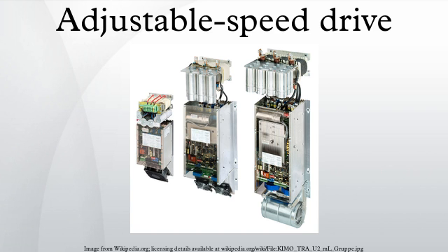Hydraulic adjustable speed drives. There are three types of hydraulic drives: hydrostatic drives, hydrodynamic drives and hydroviscous drives. A hydrostatic drive consists of a hydraulic pump and a hydraulic motor. Since positive displacement pumps and motors are used, one revolution of the pump or motor corresponds to a set volume of fluid flow that is determined by the displacement regardless of speed or torque. Speed is regulated by regulating the fluid flow with a valve or by changing the displacement of the pump or motor.